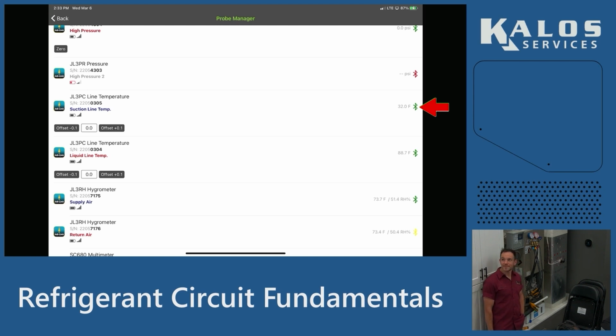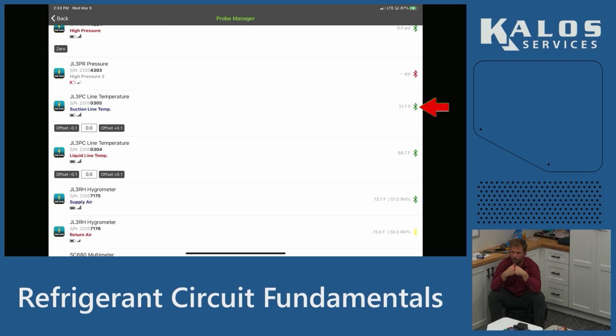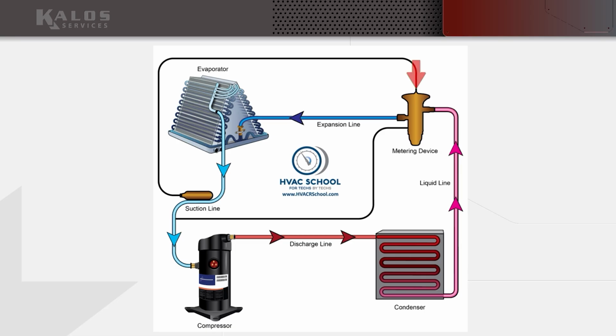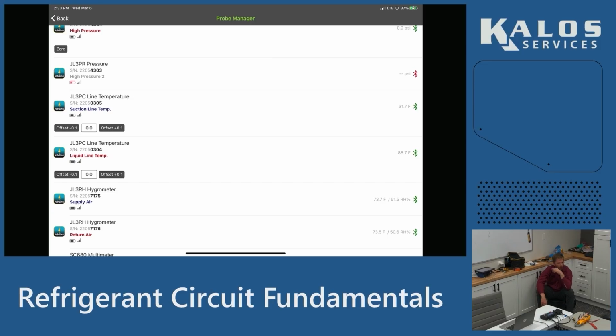So this is how low airflow, which lowers the amount of heat coming into that coil and into that refrigerant, brings the refrigerant pressure down. Part of what sets the pressure is the metering device and the compressor working together. But another part is that balance point of how much heat we're putting into it. If we're not putting heat into it, the pressure will continually drop as it gets colder and colder, because cold temperature creates lower pressure, and lower pressure creates colder temperature.